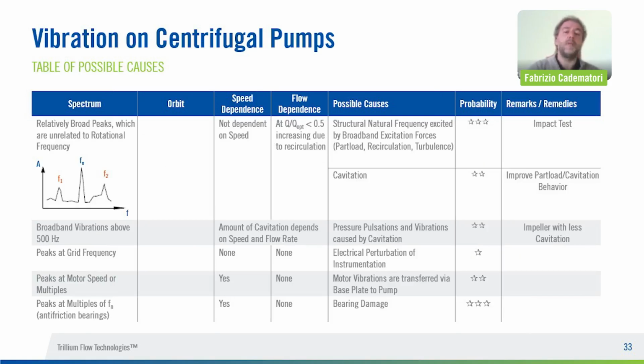Okay. Now we arrive at resonance condition. The most evident symptom of resonance is the presence of peaks in the spectrum that are not related to rotational speed. If it is possible to vary the rotor speed, the position of the peaks on the spectrum will not change. It is important to understand that resonance is not only excited by a close-by discrete excitation frequency, but also by broadband mechanisms such as partial load, recirculation, turbulence, and so on.